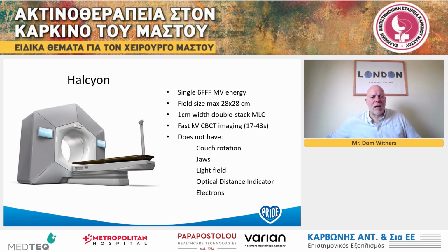It doesn't have any couch rotation, which can be an issue. It means we cannot do any matched plane treatments. If you have a so-called single isocenter treatment for breast, you can't do that on this machine. There are no jaws. That's not a problem because the double-stacked MLC already provides all of the collimation required. There is no light field, so all of the setup is being done with imaging, not with a light field or with an optical distance indicator, because there isn't one of those either. The machine has no electrons either. So it feels like it might not be very versatile, but we use it for every indication in our hospital, and I say quite successfully too.